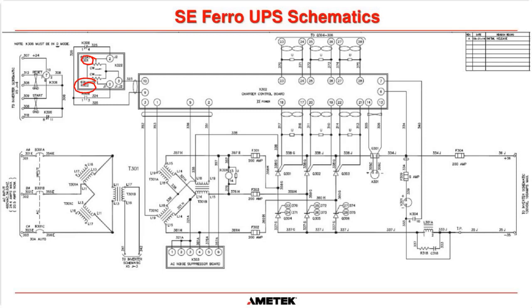On this system here, there is a timer circuit, so this has an auto equalize function. If they lost power for a set time, whatever you set the timer for, then when power comes back on again, it will start the system in equalize mode for a certain length of time. And basically the float pot and the equalize pot send back the reference signal. This is a reference signal for the voltage. So this is where you set float to 135 and equalize to 140, usually, but check your battery manufacturer data sheet to make sure.